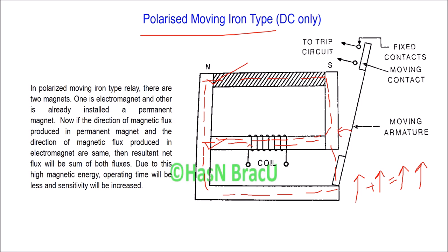This means the operating time will be less and sensitivity will be increased. On the other hand, if the direction of the magnetic flux produced by the permanent magnet and the direction of the magnetic flux produced by the electromagnet are opposite, the resultant flux will be decreased, and magnetic energy will be decreased. This means the polarized moving iron type relay will only operate if the direction of both fluxes are the same. This provides a directional feature of the relay, due to which the polarized moving iron type relay is basically used in DC systems.